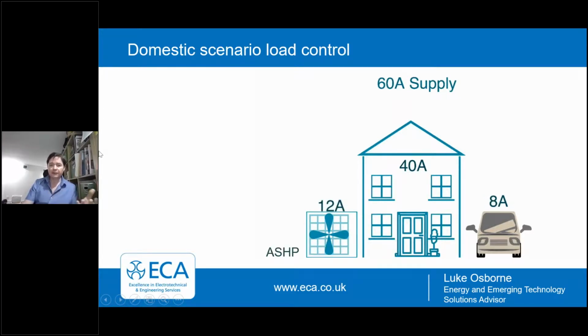If you had a 60 amp supply to a property and the house was using 40 amps, that would leave 20 amps available to the car. Now, if an air source heat pump came on, with the house still using 40 amps, and 12 amps going to the air source heat pump, that reduces down to 8 amps for the car. As the load in the property reduces, that will then increase the load available to the car. As you can see in this instance, that has then gone up to 26 amps.